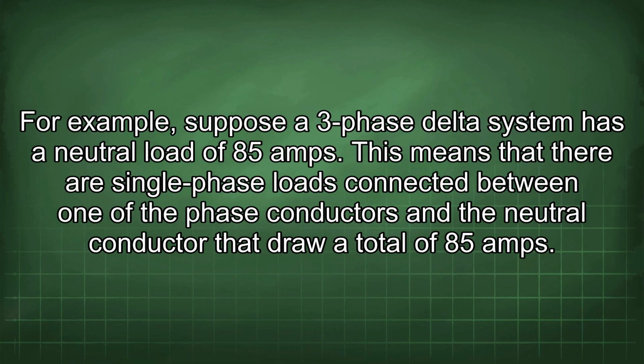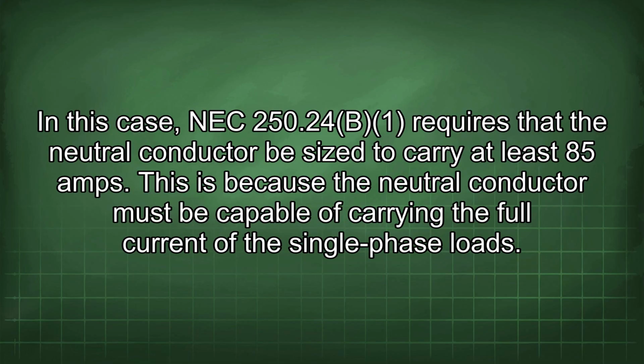For example, suppose a three-phase delta system has a neutral load of 85 amps. This means that there are single-phase loads connected between one of the phase conductors and the neutral conductor that draw a total of 85 amps. In this case, NEC 250.24(B)(1) requires that the neutral conductor be sized to carry at least 85 amps. This is because the neutral conductor must be capable of carrying the full current of the single-phase loads.